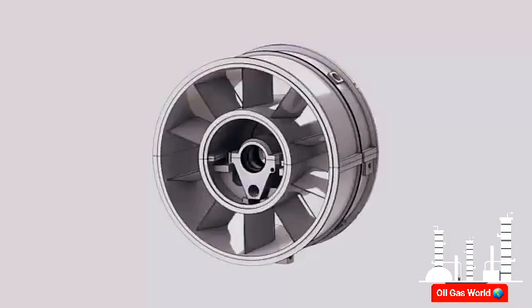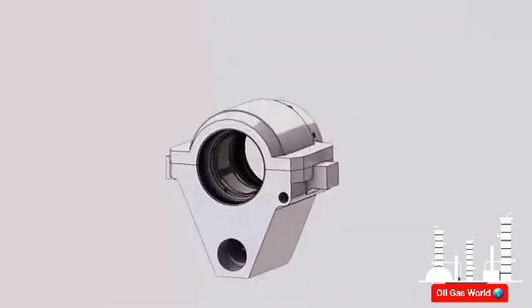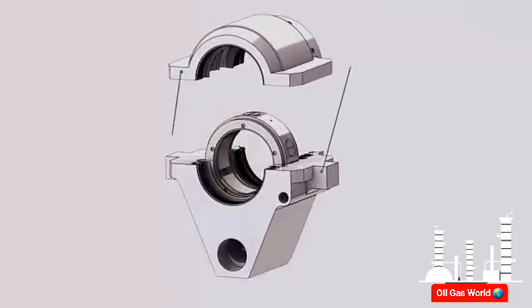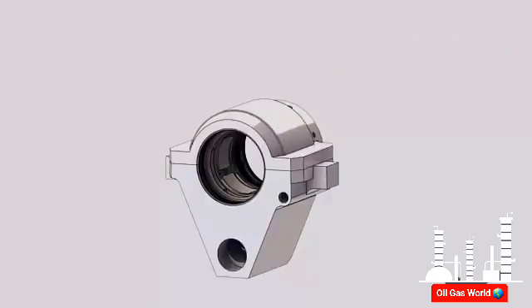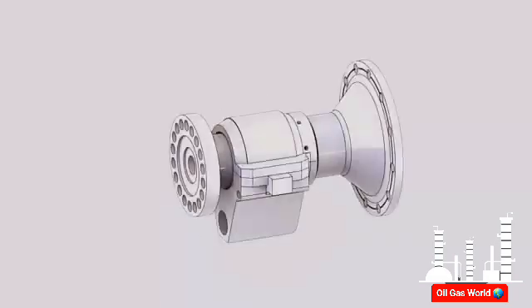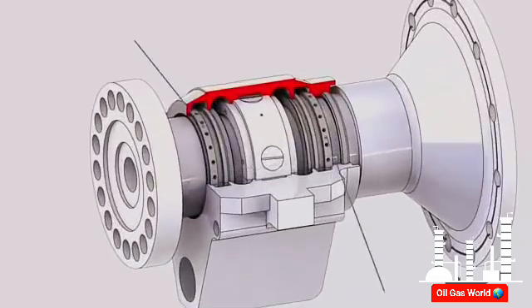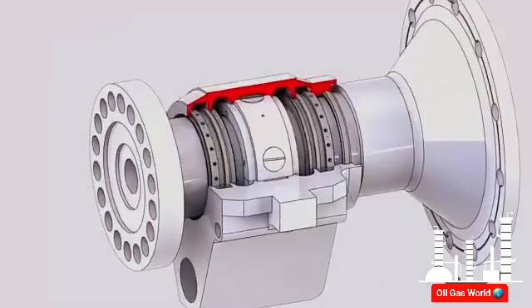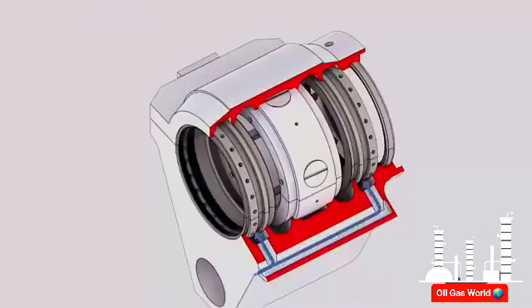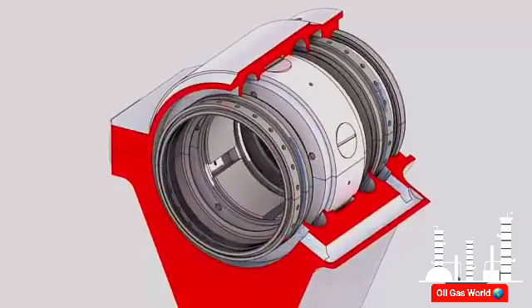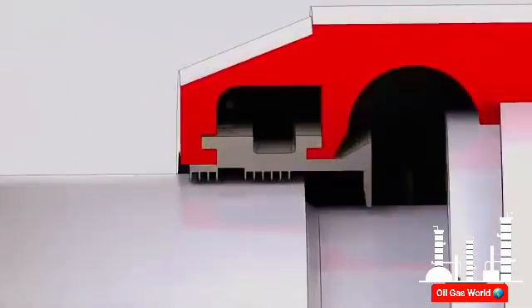Bearing 3 is located at the aft end of the turbine in the center of the exhaust frame. The bearing components are installed inside the bearing housing which consists of the lower and upper halves. Bearing 3 is a tilting pad journal bearing. This type of bearing is used in situations where slight misalignment is expected. Labyrinth seals are installed in the housing where oil control is required. Their teeth run against rotor smooth surfaces. The sealing air flows from the cooling and sealing system through the axial tube machined at the left side of the housing and is admitted to the labyrinth seals through two ports to annular spaces surrounding the seals, between the two rows of seal teeth. Similar to other bearings, sealing air is admitted through multiple radial holes to stop oil leakage.